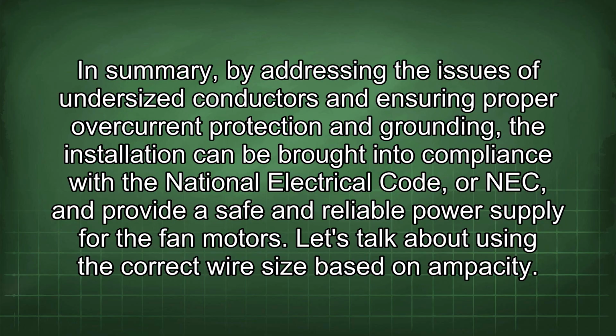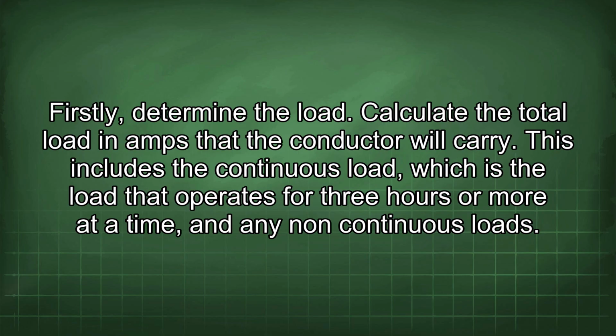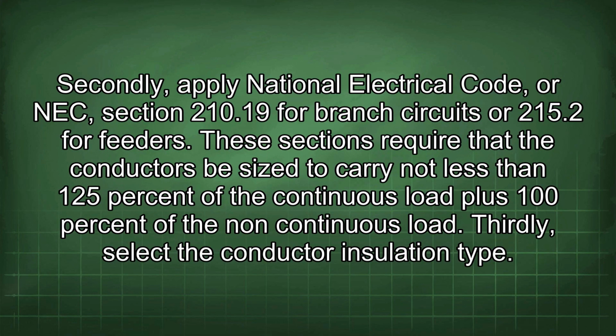the fan motors. Let's talk about using the correct wire size based on ampacity. Firstly, determine the load. Calculate the total load in amps that the conductor will carry. This includes the continuous load, which is the load that operates for 3 hours or more at a time, and any non-continuous loads. Secondly, apply NEC Section 210.19 for branch circuits or 215.2 for feeders.